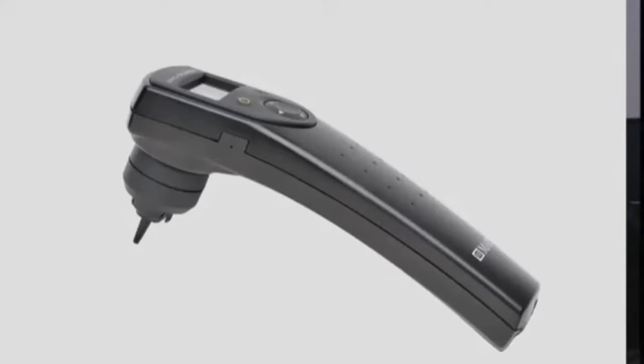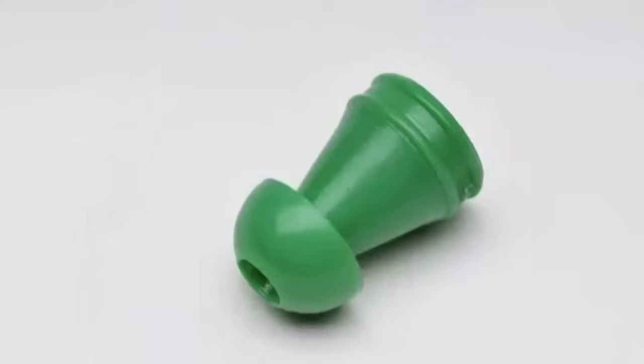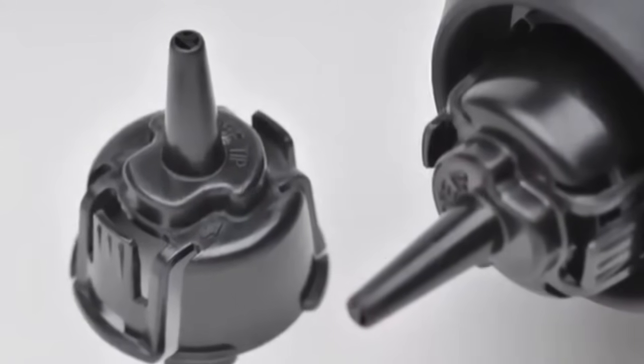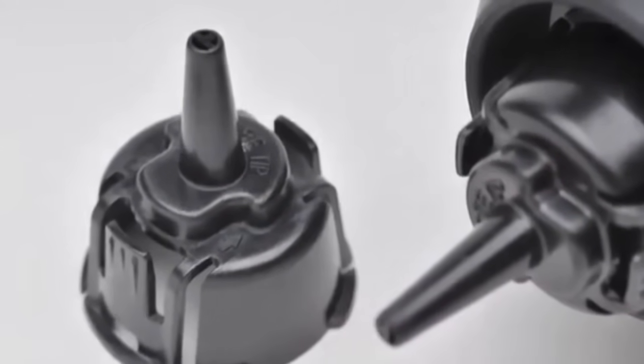The probe consists of 3 main elements: the probe assembly, the probe tip, and the ear tip. The probe assembly incorporates the microphone that senses the OAE information present in the ear canal, as well as the tubing that delivers the stimulus. The probe tip is the interface between the probe head and the ear tip. These probe tips are disposable and should be replaced when they get clogged by earwax or other material.